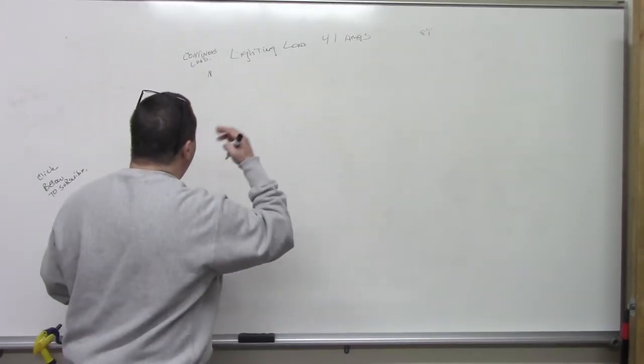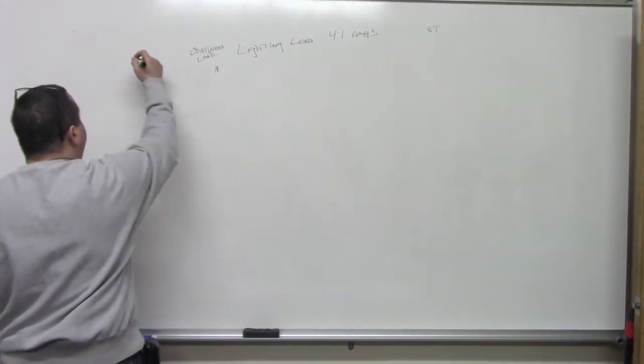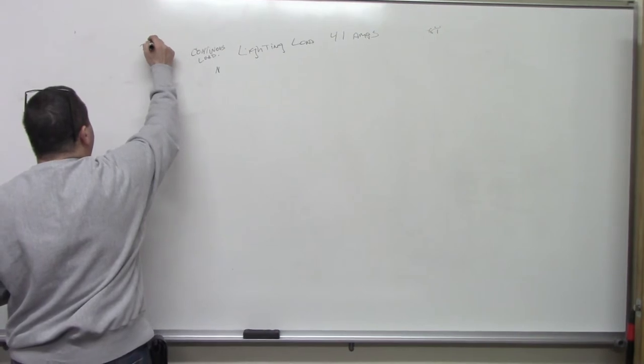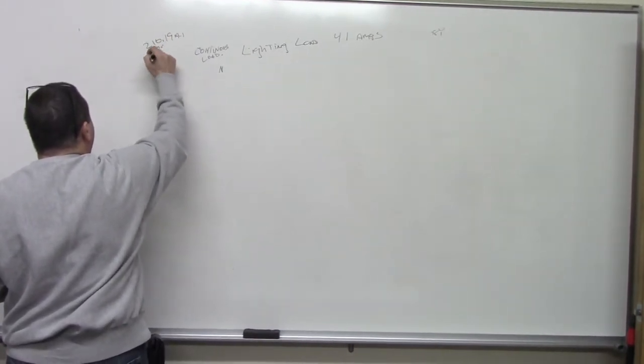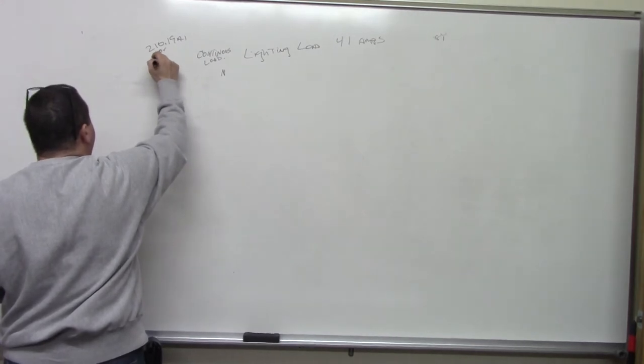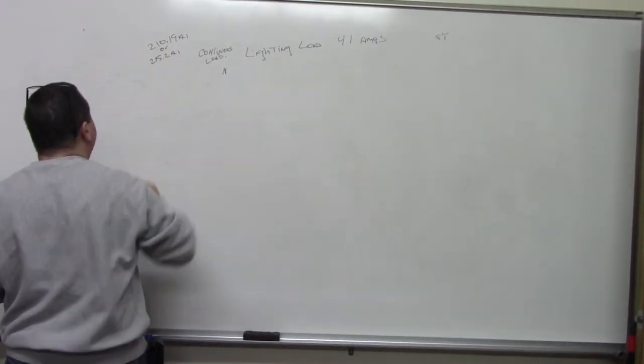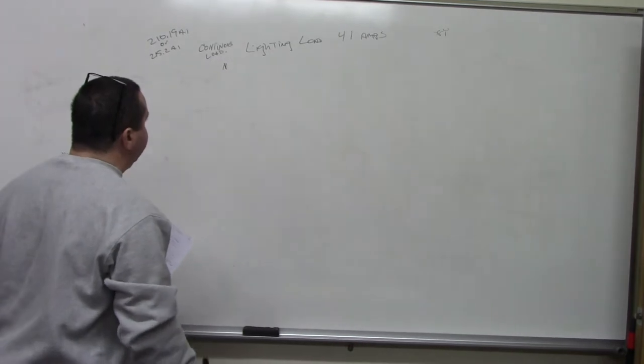So continuous load, and we'll talk, and again, continuous load for this is based on 210.19A1 or 215.2A1, okay? That's where you'll find continuous load.